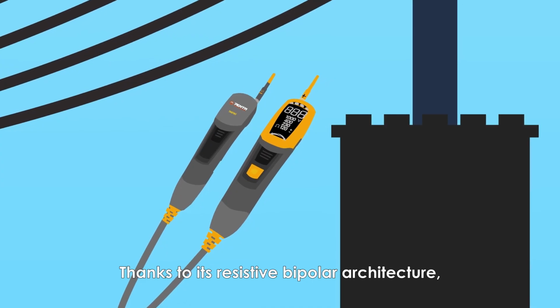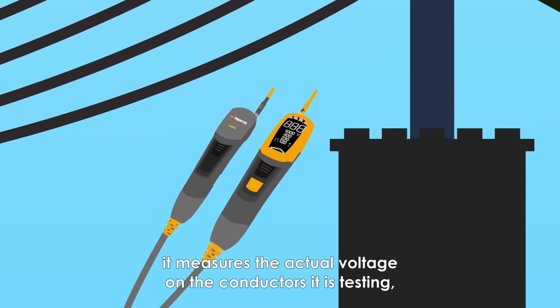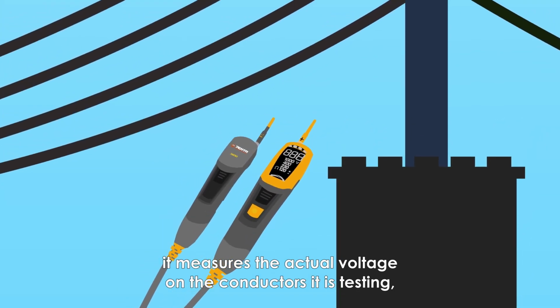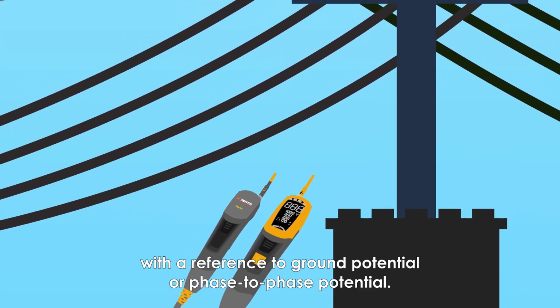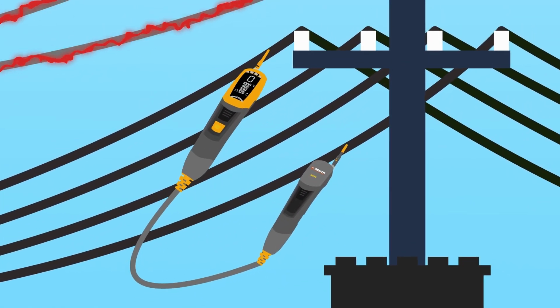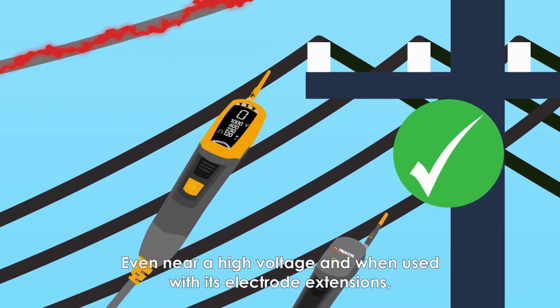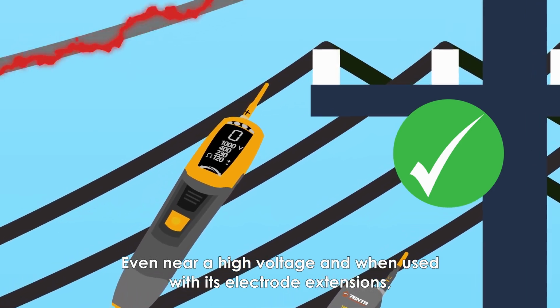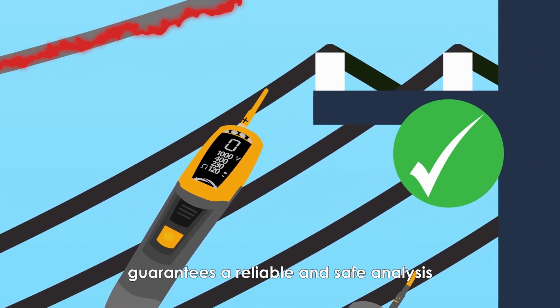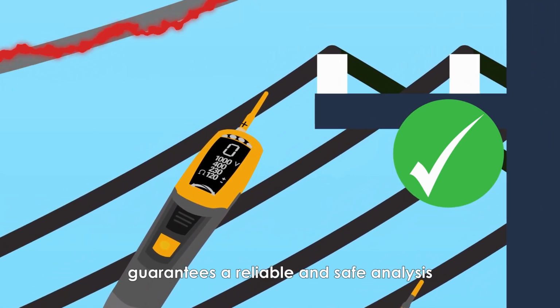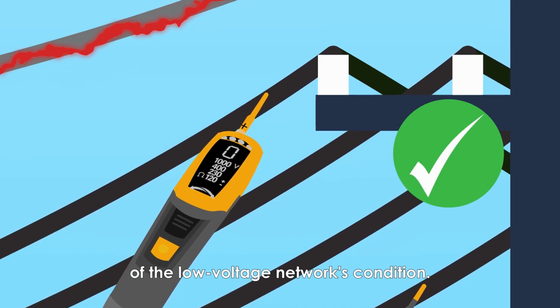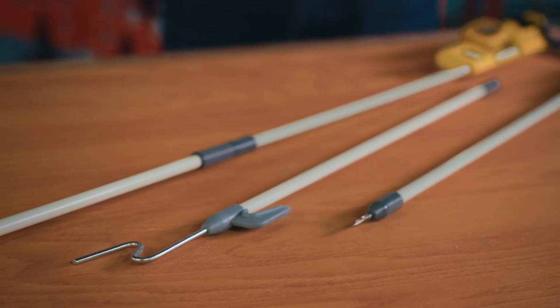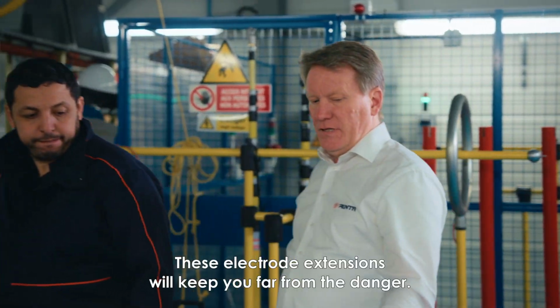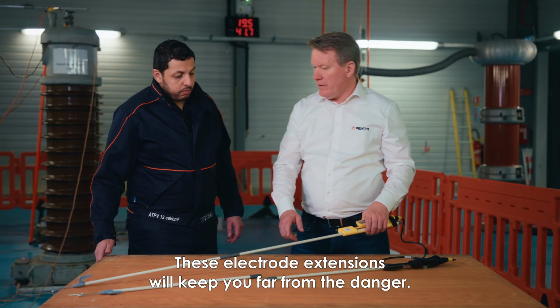Thanks to its resistive bipolar architecture, it measures the actual voltage on the conductors it is testing, with a reference to ground potential or phase-to-phase potential. Even near a high voltage, and when used with its electrode extensions, the Penta low voltage detector guarantees a reliable and safe analysis of the low voltage network's condition. These electrode extensions will keep you far from the danger.